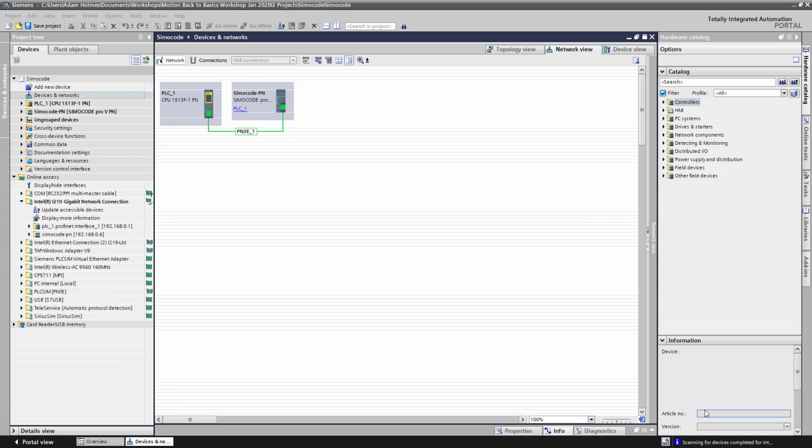What that means is we will put the new device into the field, reconnect the programming cables or reconnect the network, and the device will get its original parameterization directly from the PLC, meaning that the engineer doesn't have to have any tools to be able to replace the device, or any programming software or capabilities. It also increases machine availability, plant uptime, so on and so forth.